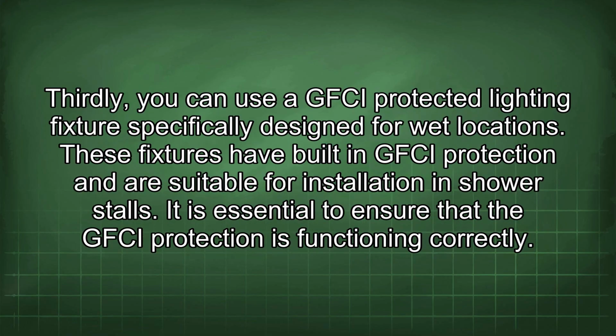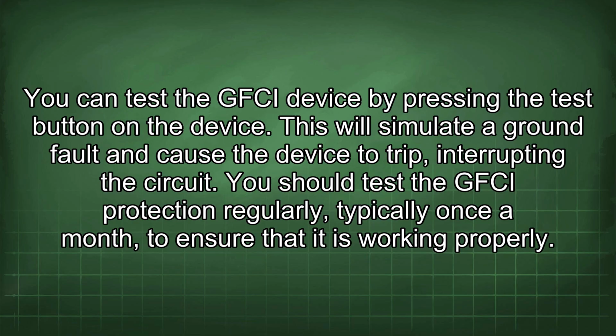Thirdly, you can use a GFCI protected lighting fixture specifically designed for wet locations. These fixtures have built-in GFCI protection and are suitable for installation in shower stalls. It is essential to ensure that the GFCI protection is functioning correctly. You can test the GFCI device by pressing the test button on the device. This will simulate a ground fault and cause the device to trip, interrupting the circuit. You should test the GFCI protection regularly, typically once a month, to ensure that it is working properly.